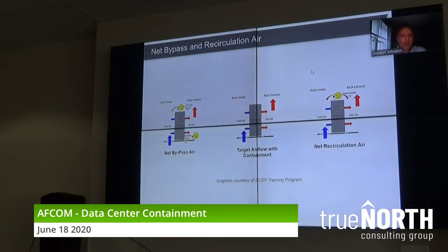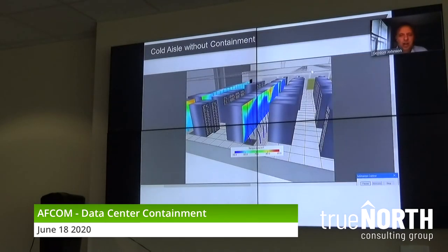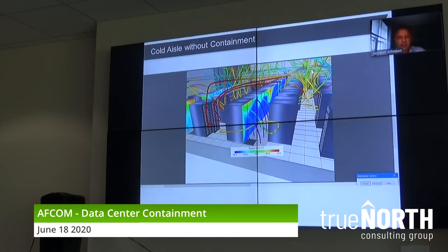The next two slides kind of bring it home with some CFD modeling. The first slide, live video, you'll see air coming in a cold aisle, 62 degrees is the supply air. Notice it's going into the racks, but notice the top of the racks. I've got 75 degree, 80 degree. And notice why. Hot air is circulating, you'll see around the end of the aisles, over the top of the racks, and back into the cold aisles.